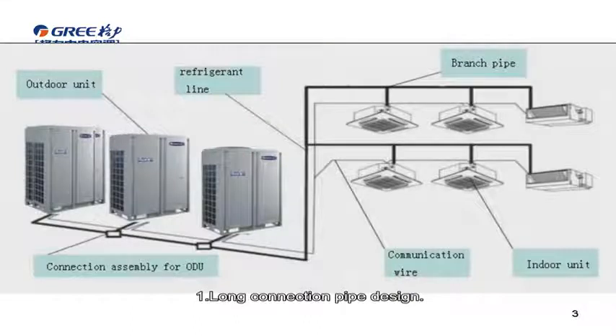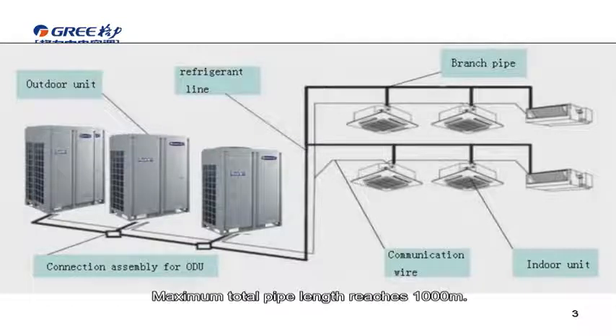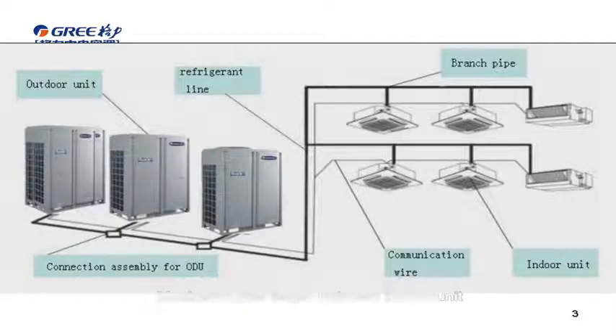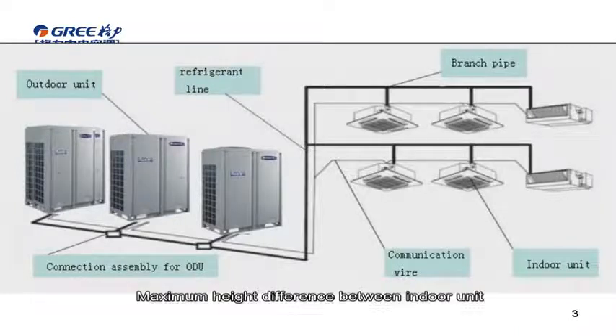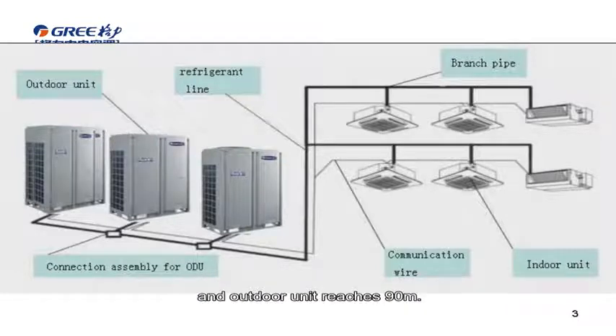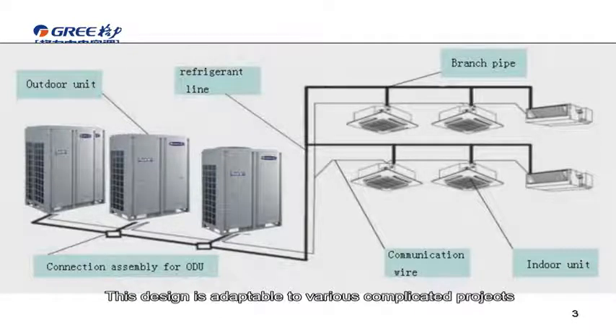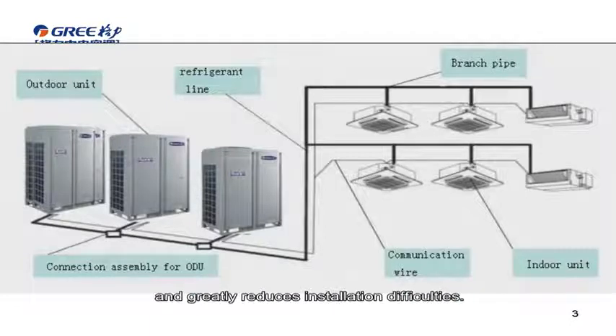The first part, product introduction, product installation features. Firstly, long connection pipe design. GMV5 applies long connection design. Maximum total pipe length reaches 1,000 meters. Maximum pipe length between indoor unit and outdoor unit reaches 165 meters. Maximum height difference between indoor unit and outdoor unit reaches 90 meters. Maximum height difference between indoor units reaches 30 meters. This design is adaptable to various complicated projects and greatly reduces installation difficulties.